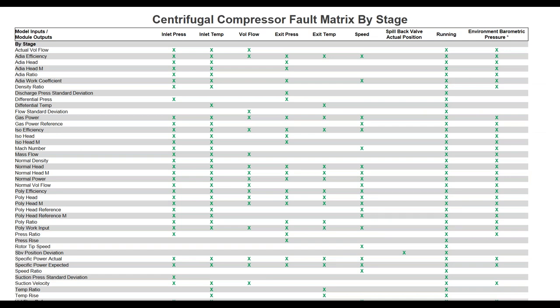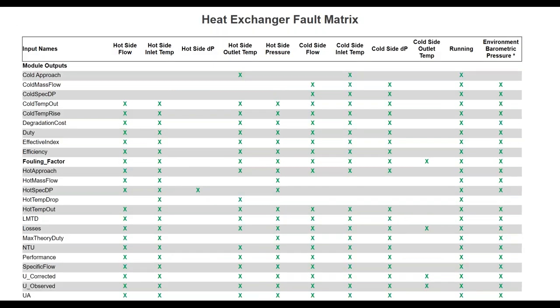Examples include a centrifugal compressor template and a heat exchanger template. The fault matrix is read with inputs as columns and KPIs as rows — for a heat exchanger these include cold approach, mass flow, and others. If you have the measurement, you get the KPI directly. If not, the platform can generate a soft sensor — a simulated input based on interpolation — or give you flexibility to remove that input entirely.